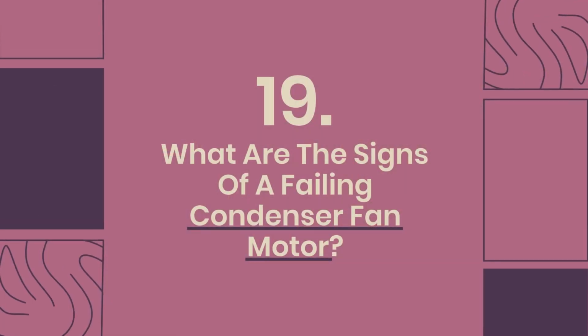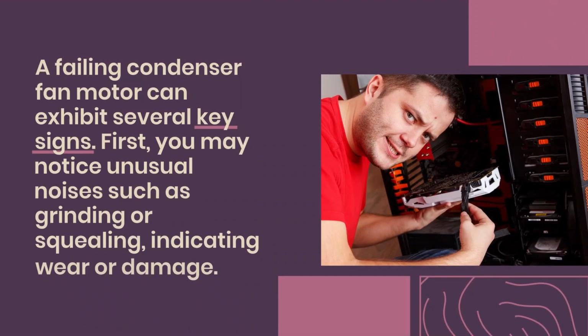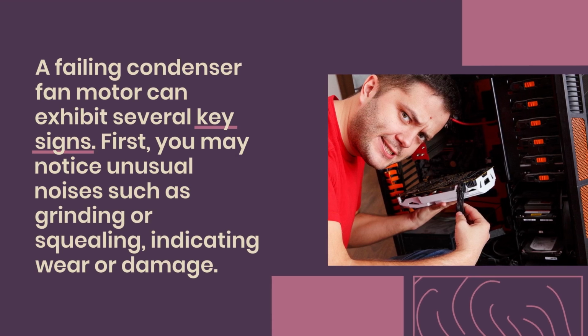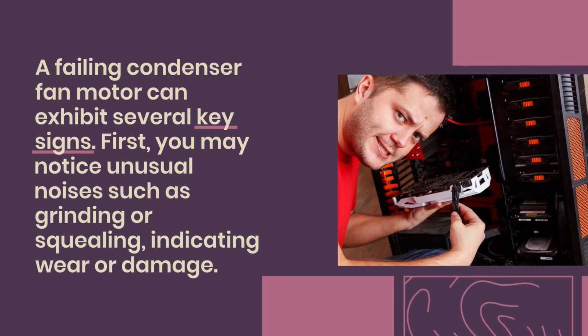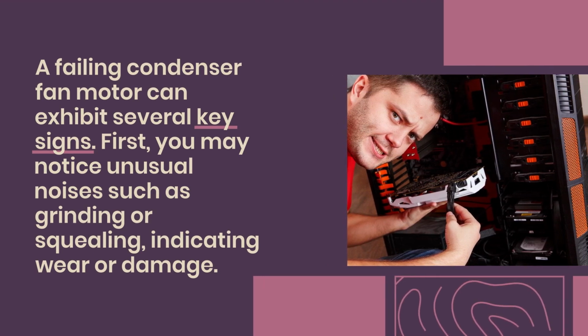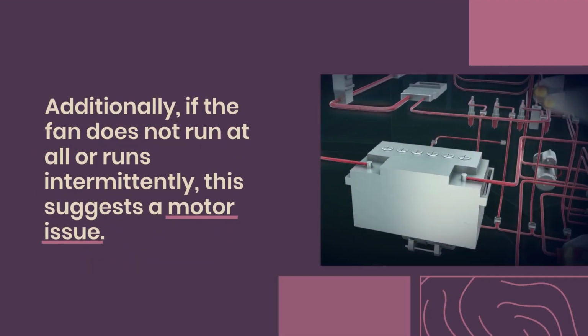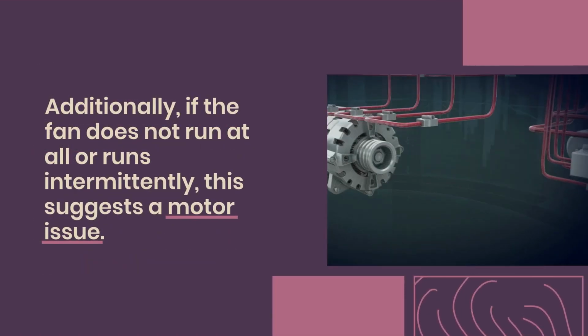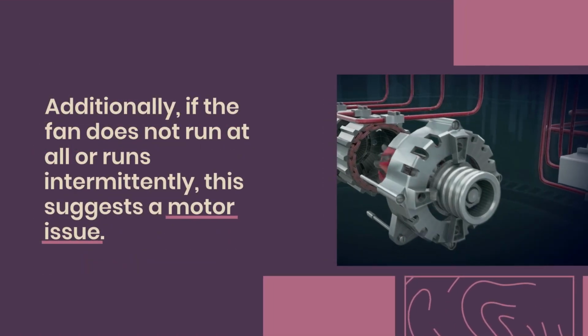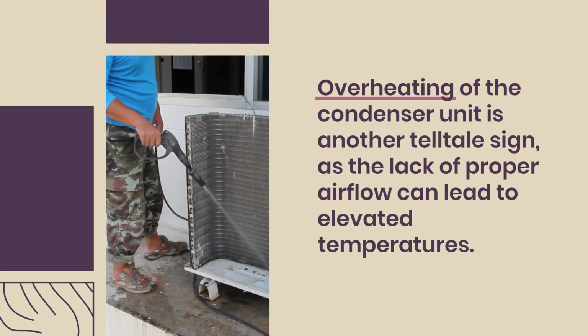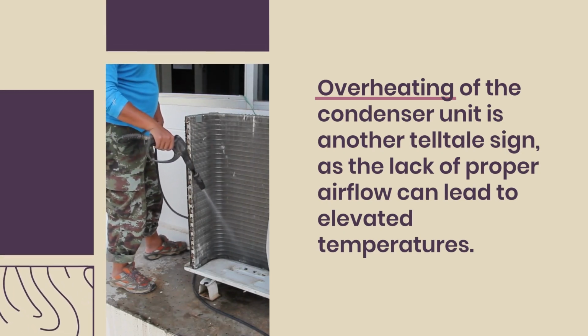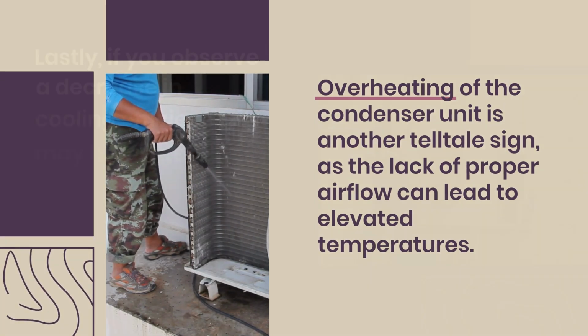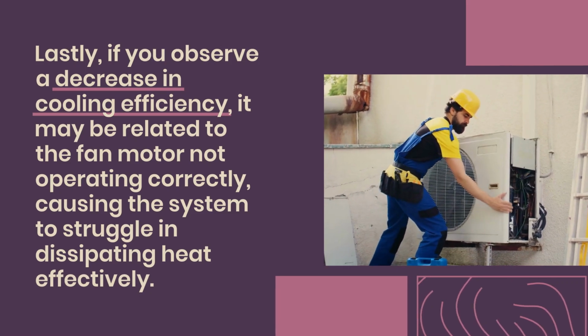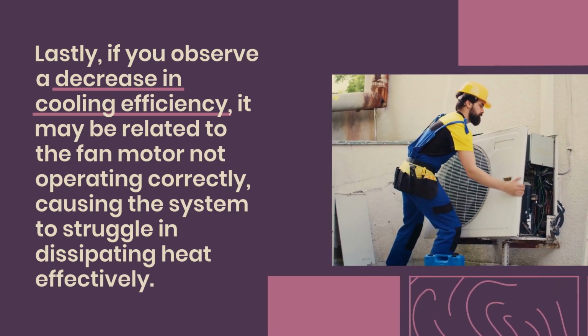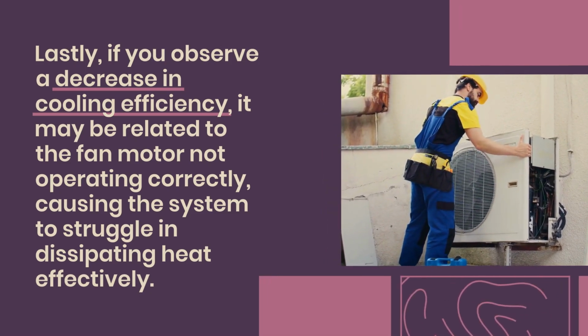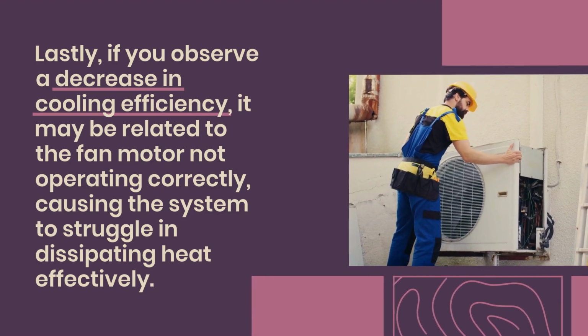19. What are the signs of a failing condenser fan motor? A failing condenser fan motor can exhibit several key signs. First, you may notice unusual noises such as grinding or squealing, indicating wear or damage. Additionally, if the fan does not run at all or runs intermittently, this suggests a motor issue. Overheating of the condenser unit is another telltale sign, as the lack of proper airflow can lead to elevated temperatures. Lastly, if you observe a decrease in cooling efficiency, it may be related to the fan motor not operating correctly, causing the system to struggle in dissipating heat effectively.